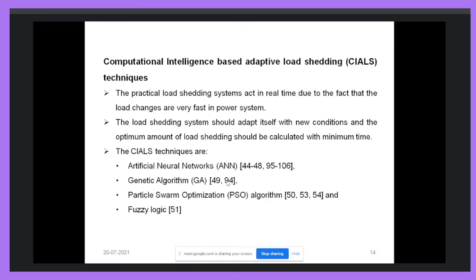Now we come to the computational intelligence based load shedding technique. A practical load shedding system acts in real time, because we have to maintain load and generation balance in real time. So the system must operate in real time and it must also be fast. The load shedding system should adapt itself to new conditions, meaning new operating conditions. As and when the load and generation change, the system must also adapt to this change.